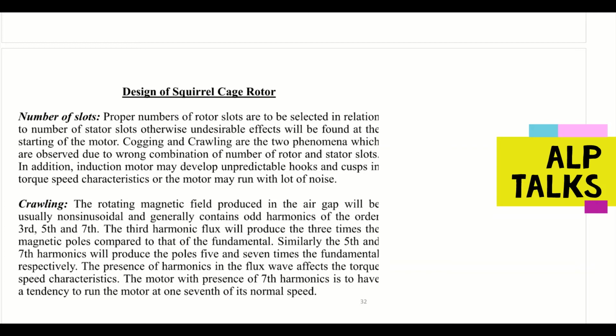So, we are going for the design of squirrel cage rotor. Here we are discussing the design of squirrel cage rotor. So the number of slots, again we have to decide. A proper number of rotor slots is to be selected in relation to the number of stator slots, otherwise undesirable effects will be found at the starting of the motor.